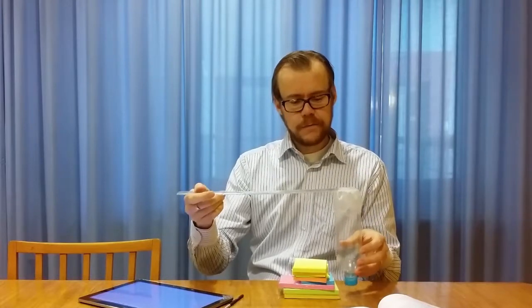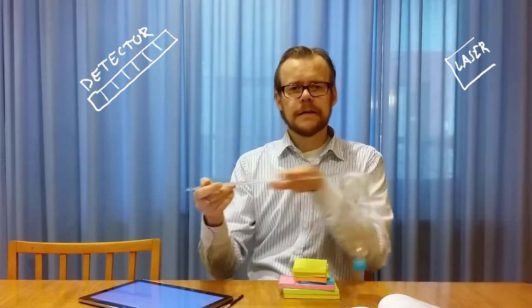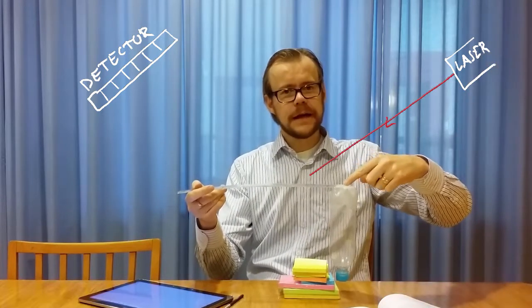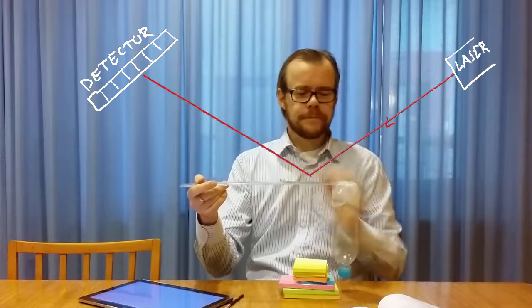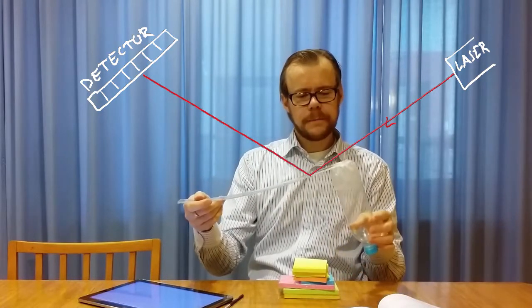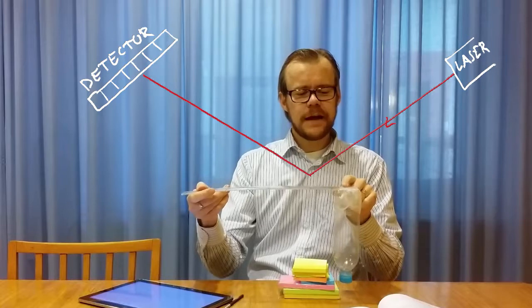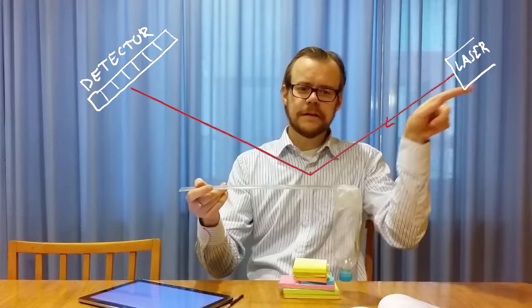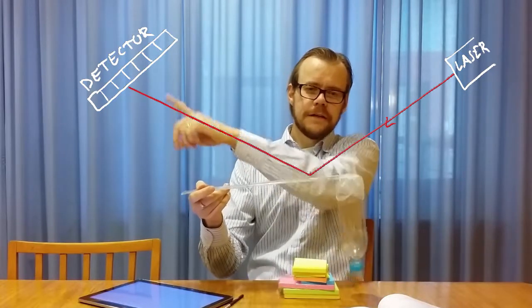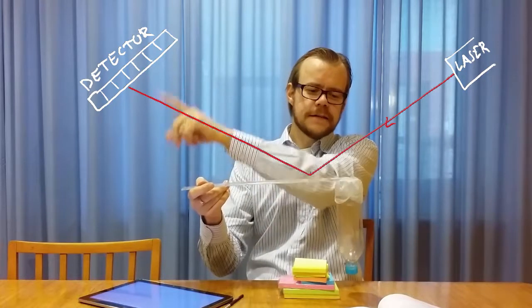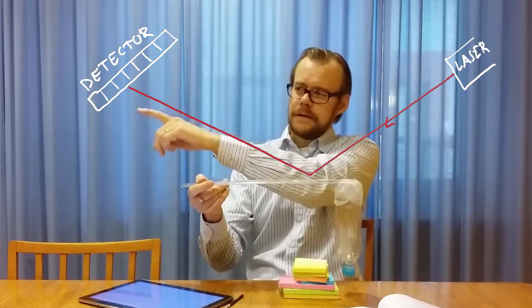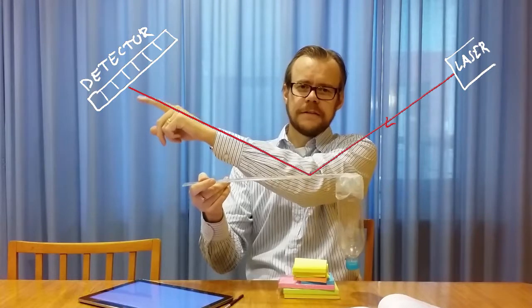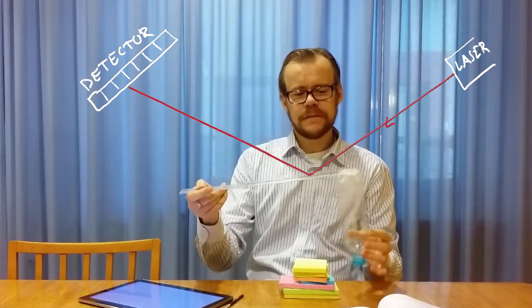Well, one very common way is to use lasers. You make this top surface of the tip mirror-like, so you put a reflective coating on top of here. You shine a laser down here and up to a sensor that you have here. Then you will see when the tip deflects up like this, it will change the angle of the surface. That means that the laser will take a different trajectory if we change the angle of this mirror. And that means the location of the laser on this sensor will be at a different position if this deflects.